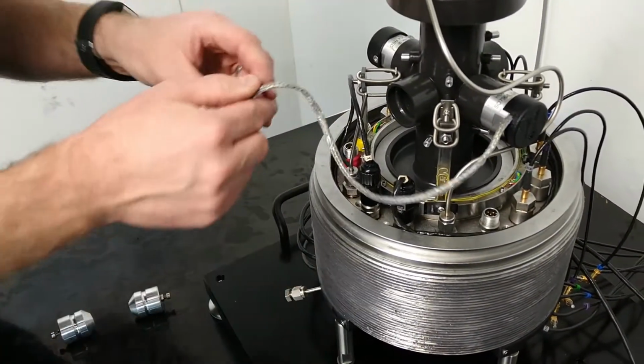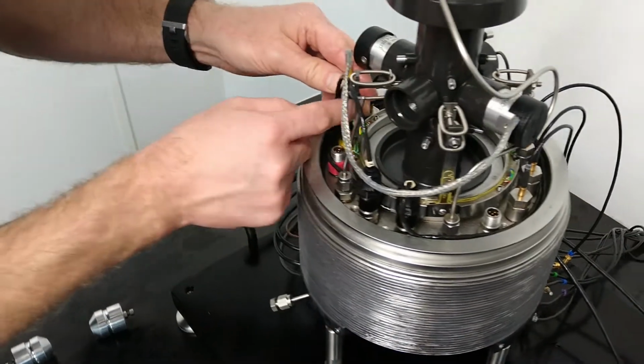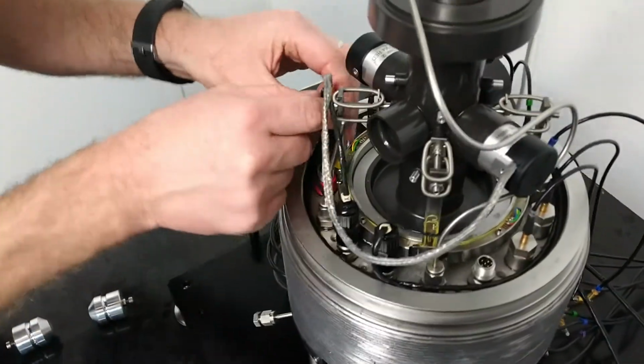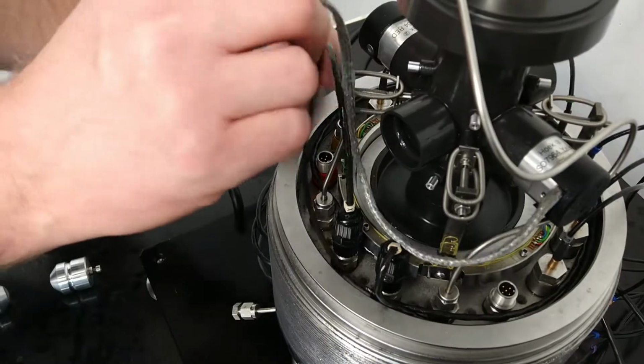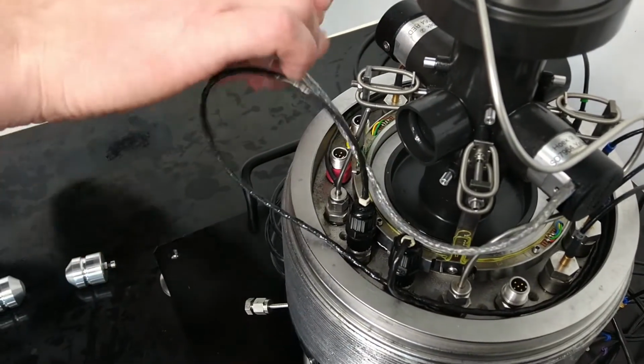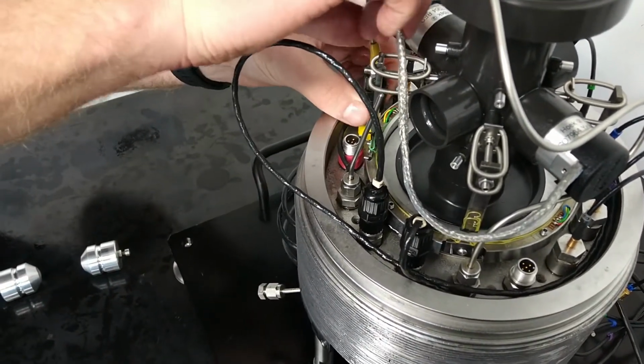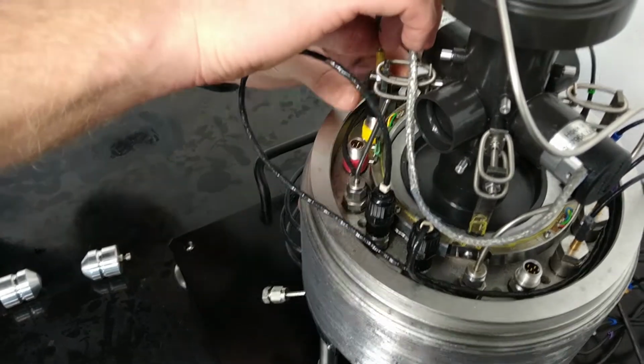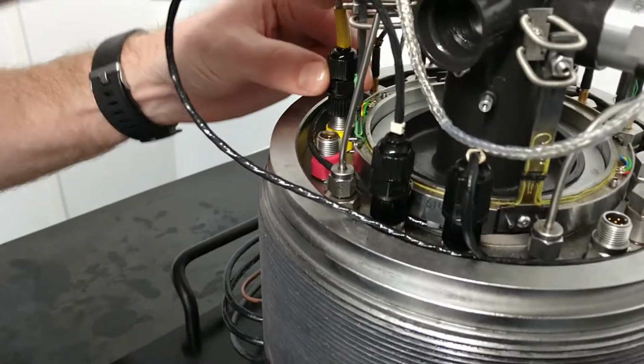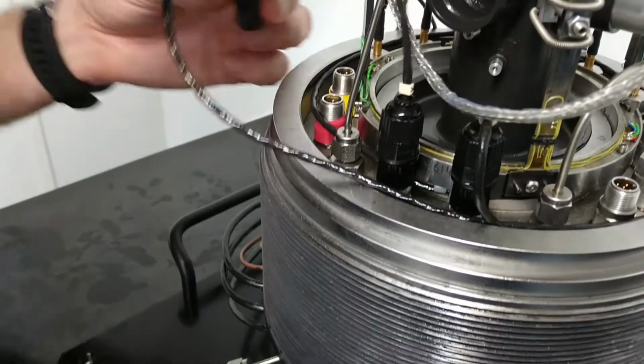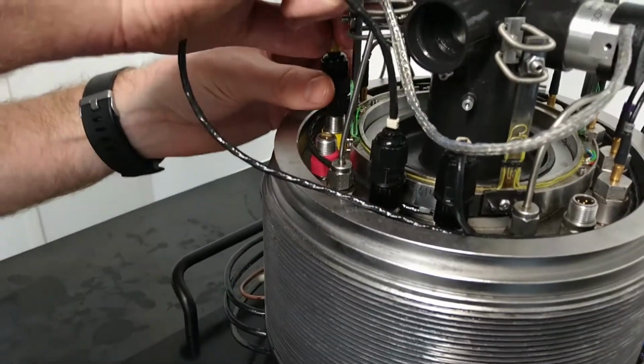Connect both the red and yellow plugs into the corresponding feed-through. To connect the feed-through plug, lightly insert the plug in the correct orientation. The plug should locate in place by dropping down slightly. Do not force the plug further, as it will locate more securely when the collar is tightened.